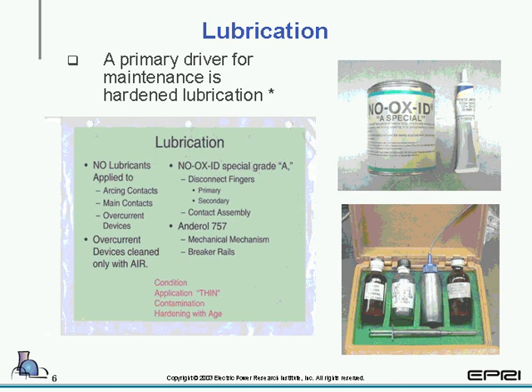One of the main items to keep in mind is a primary reason breakers tend not to work is hardened lubrication. It tends to fail in the breaker before parts, or the electric parts, or the contact. That seems to contradict what we just said, but really lubricant is embedded throughout the operating mechanism, and you can't really get to it during the PM. So if you're PMing a breaker, there are sections of that operating mechanism you will never even see or touch.